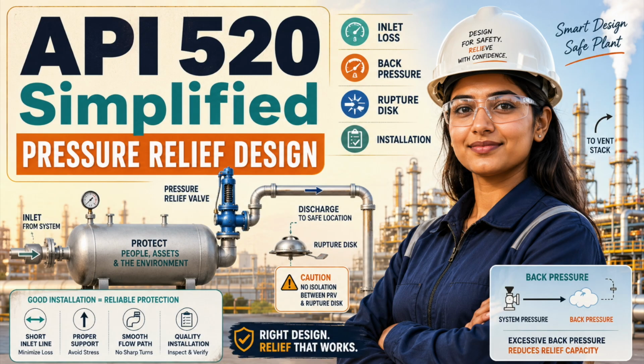Now consider the device itself. A conventional spring-loaded valve is simple, proven, and effective when the service suits it. Process pressure acts against spring force, the valve opens near set pressure, and it recloses after the pressure falls sufficiently. Its main weakness is back pressure sensitivity. If the outlet is connected to a flare or common relief header, you need to know the superimposed back pressure before the valve opens and the built-up back pressure created after flow begins.